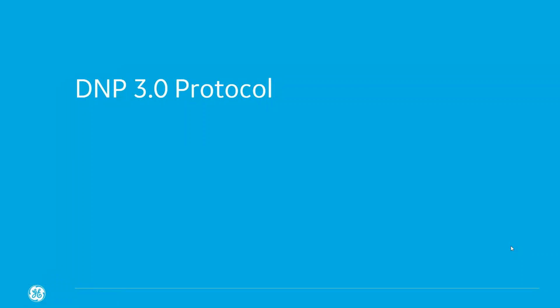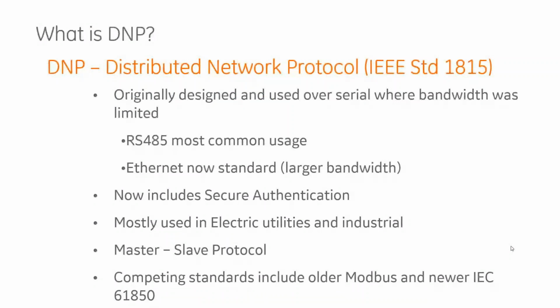So the protocols that we use on serial for legacy serial networks are DNP. 3.0 is the recent version. Distributed Network Protocol, it's now an IEEE standard, 1815. When it first came out, it was not an IEEE standard. The most common usage in our brownfield projects today is using it over an RS-485, which is that multi-drop architecture I showed previously. However, you could also use DNP if you have an Ethernet communication now, to be able to take advantage of some of the higher bandwidth that you have over Ethernet. So DNP, the standard has been adjusted to include Ethernet as one of the communication mediums.